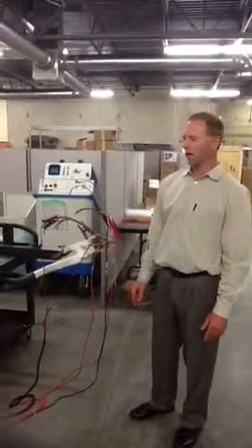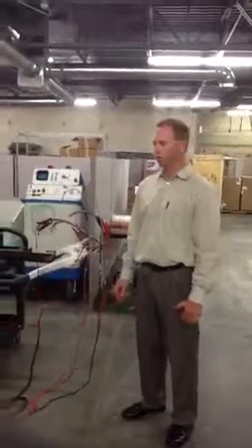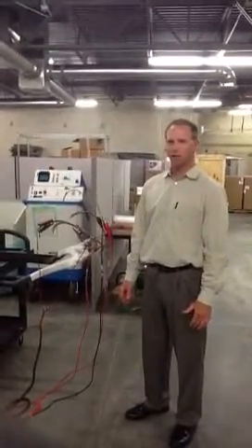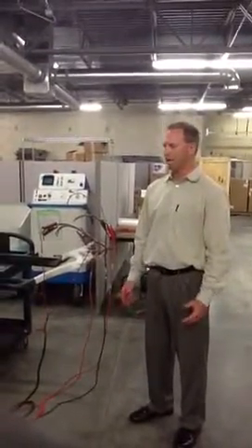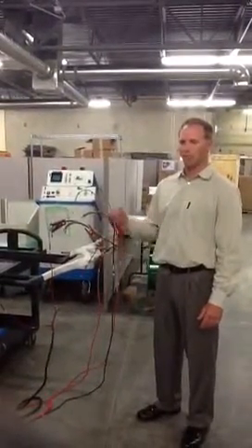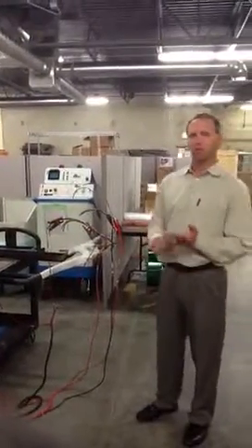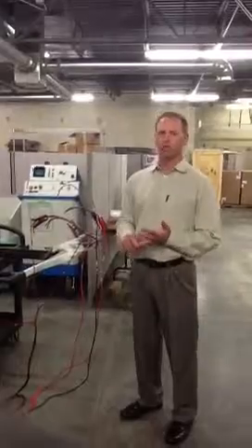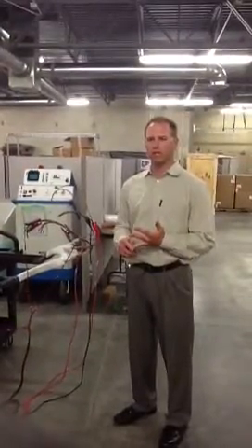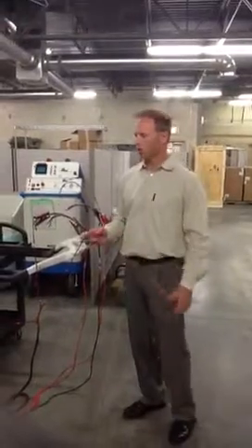Today we're going to show how to perform a series of automatic tests with the AWA on individual coils. The AWA has the ability to set up a test ID so that everybody that performs these tests will perform them the exact same way. The test IDs house the particular test that you want to run, the voltages you want to ramp up to on each test, and the pass-fail criteria. So what we're going to show today is how to set up these test IDs.